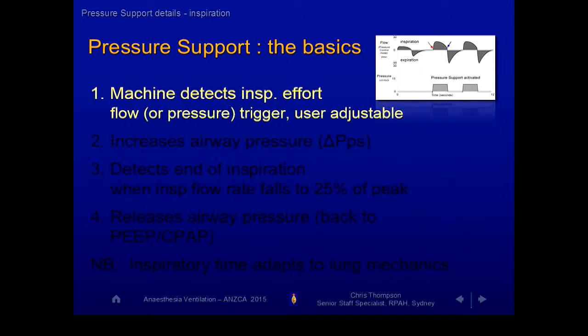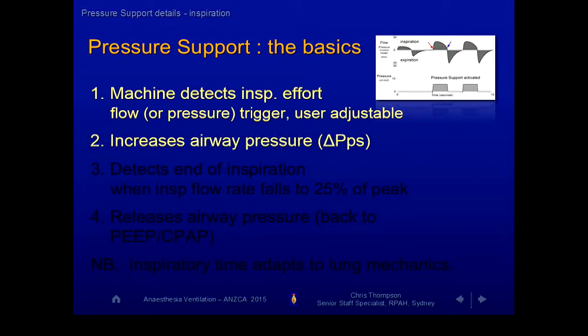I'd like to talk about pressure support. For those not all that familiar with it, the basics are that it detects inspiratory effort by looking at a flow trigger. So when the machine realizes some air's gone in, a little red arrow appears on the flow curve, ideally, and the machine then increases airway pressure and gas flows into your lungs.